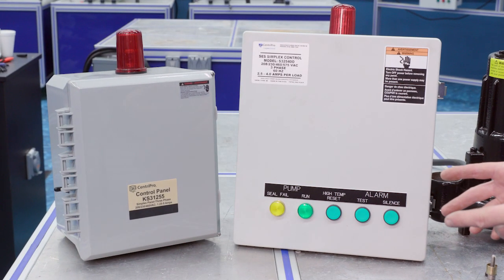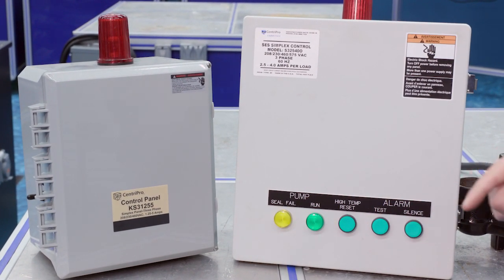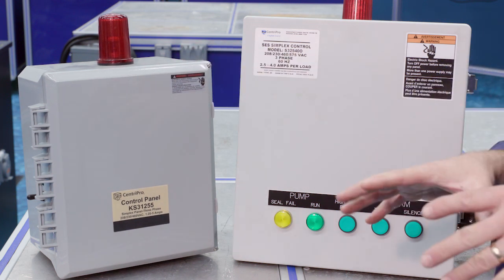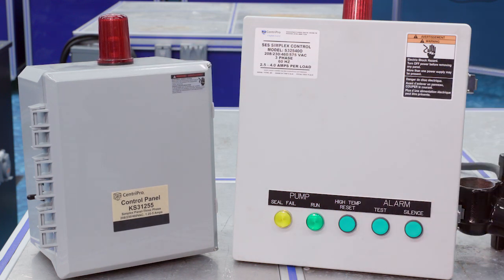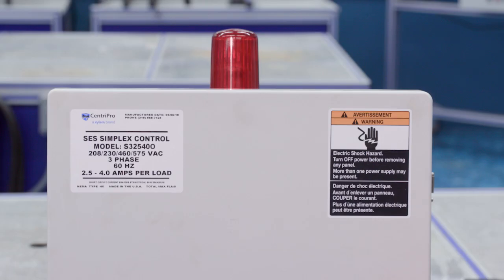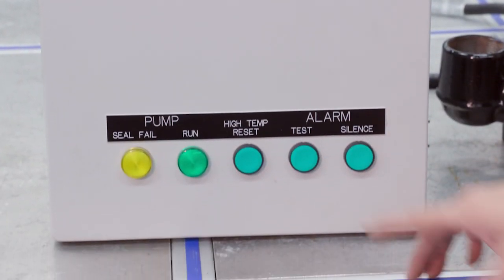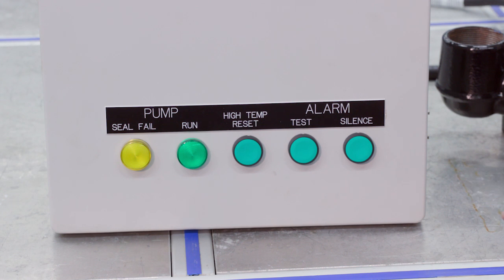For your panel, you have two basic options. Panel A would have the seal fail sensor in the panel and the thermal sensor in the panel, so there would be notification of an issue with the thermal or the leak detection. Panel B does not have those sensors but can still be used as an alternative. Option A would be a panel like this that has a seal fail indicator and a thermal indicator in the panel itself.